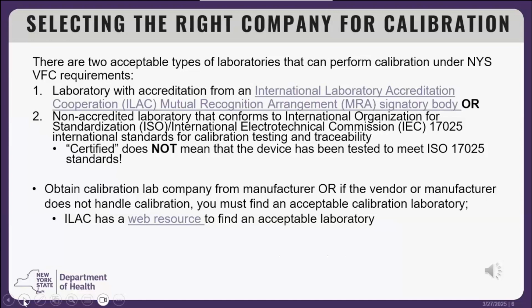Keep in mind that even if a vendor or laboratory claims to certify temperature monitoring devices, this does not necessarily mean their calibration process meets ISO 17025 standards, or that they are appropriately accredited. If the vendor or manufacturer does not handle calibration, you must find an acceptable calibration laboratory. The ILAC has a web resource that you can use to look up acceptable calibration laboratories. The link can be found on this slide, also in the resources document provided with these trainings.